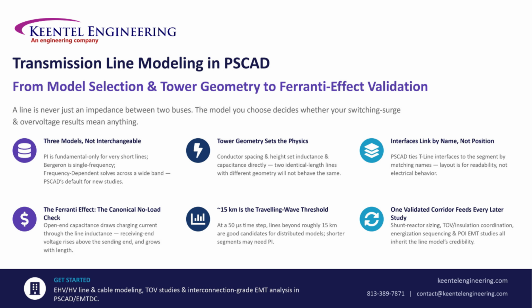Let's close out on why line model choice decides your entire study. A transmission line is never just an impedance between 2 buses. It's a distributed network of inductance, capacitance, and resistance that changes with frequency, geometry, and length. Choose the wrong model, and you miss the exact traveling wave behavior that drives switching surges and overvoltages.